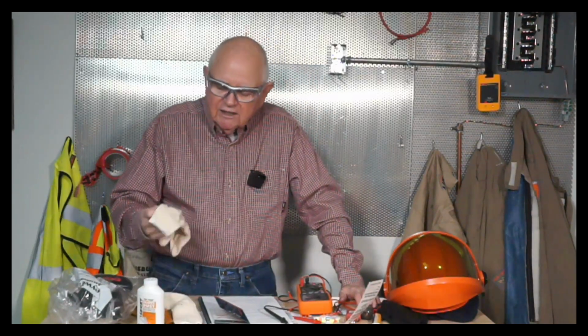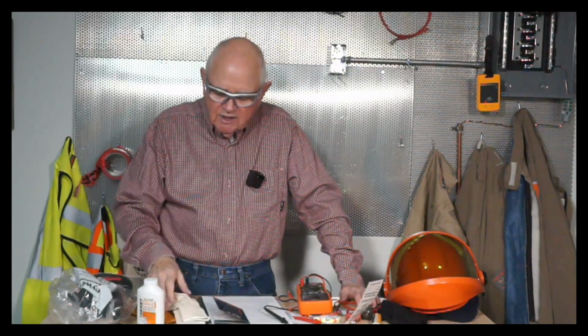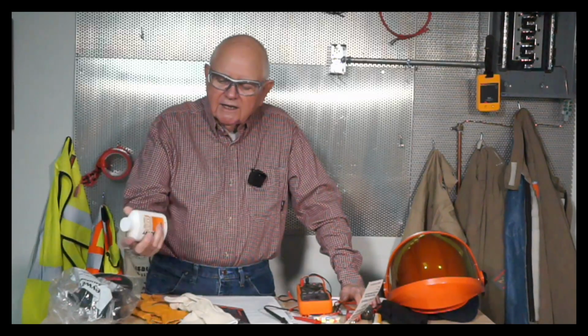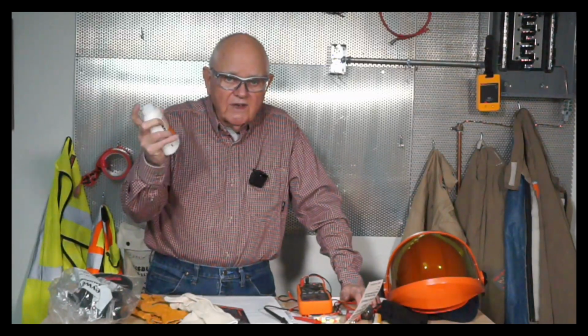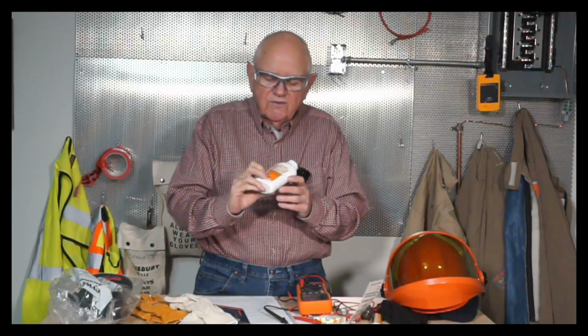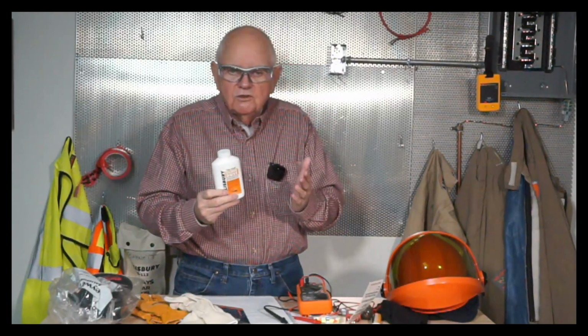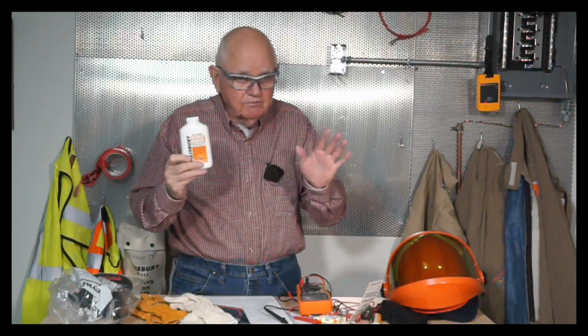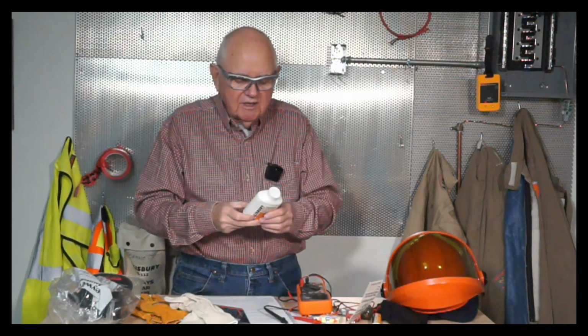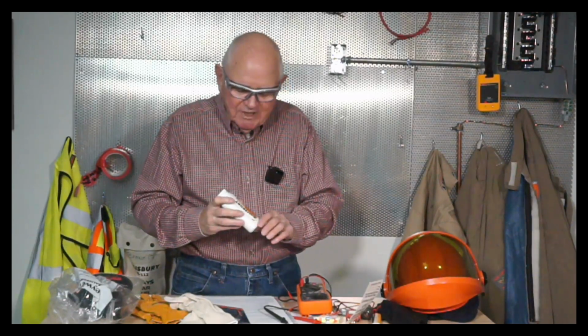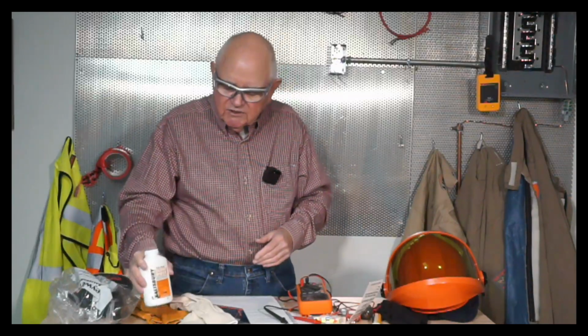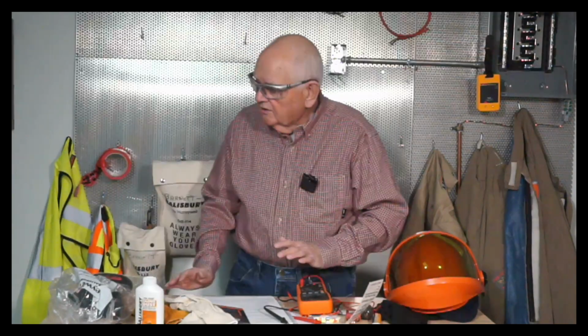I can wear cotton liners underneath my rubber gloves for comfort. That's a good thing. I can use whatever the manufacturer says for some type of powder on the inside. This is called glove dust from this manufacturer, and that's fine. I don't use things like baby powder. That's prohibited for safety reasons, okay? It's conductive and deteriorates rubber and so forth. So know your rubber gloves, inspect your rubber gloves, and make sure that they're good to use.